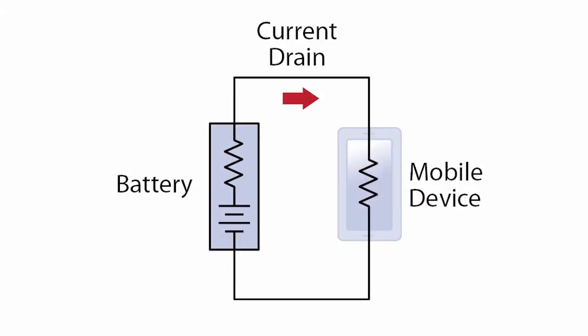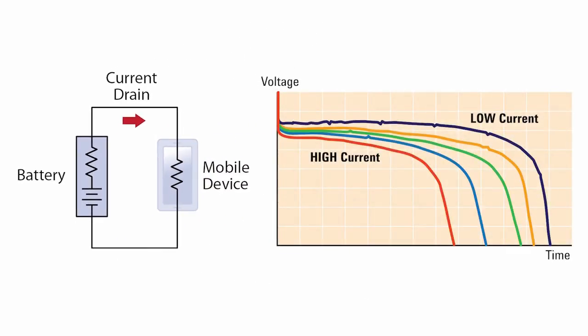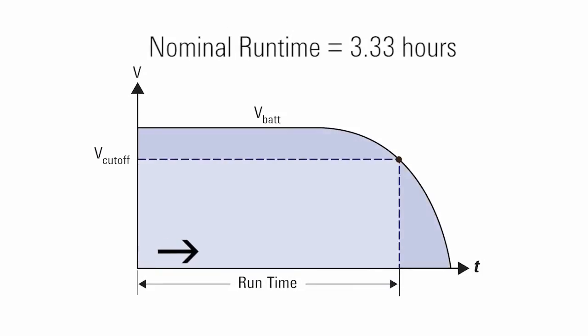One key condition is the discharge rate, or C-rate, usually stated as a constant current discharge at some ratio of the amp-hour capacity rating. A manufacturer may specify a discharge C-rate of only 0.3, for example, because higher discharge rates will lead to lower capacity and energy delivered from the battery. For a 1 amp-hour battery, a C-rate of 0.3 would be a 0.3 amp constant current discharge. Using this C-rate would theoretically discharge the battery to its cutoff voltage in 3.33 hours.